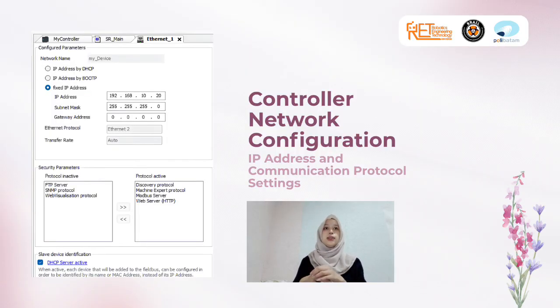The next slide is to configure the Ethernet network. So it's like a controller network configuration. In here, I configured the Ethernet network for the Modicon M241 controller. I use a fixed IP address, that is 192.168.10.20, with a subnet mask 255.255.255.0.